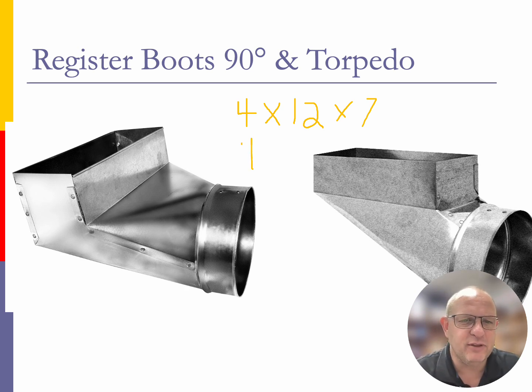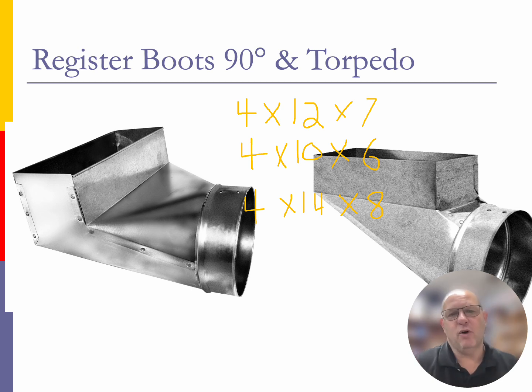Now there are a couple of different sizes of boots that are out there. And I'm just going to write them down on the PowerPoint right here. And you go ahead and write them down because as you're doing your ductwork project, you're going to want to put these particular boots into the rooms based off the type of round pipe that's running into them. Now, 4 by 12 by 7, that's the normal pipe size for a 4 by 12 register.